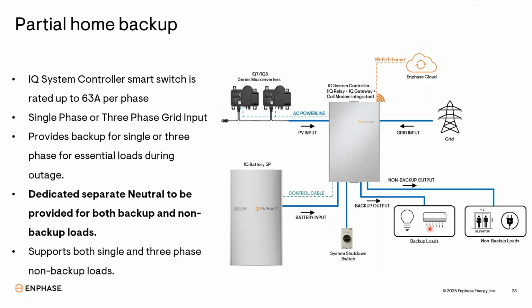Partial home backup means you are only backing up some essential loads like your lights, fan, fridge, AC, or some appliances in the kitchen. You're not going to back up your heavy loads like power sockets, your lift, your heat pumps, your dryers, or your submersible pumps. Those types of loads you do not want to back up. In that scenario, the connection will be the same. Only there will be one more output from the controller, which is the non-backup loads. You take your heavy appliances on the non-backup loads. Here also the bus bar supports a maximum of 63 amps, so whatever you are designing, make sure you design under this limit only.